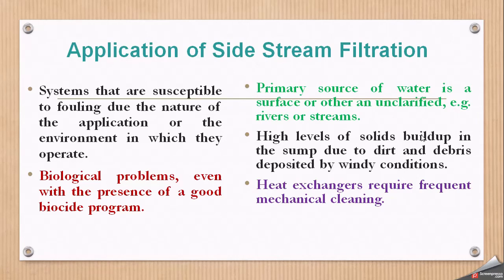High levels of solid buildup in the sump due to dirt and debris from windy conditions or dust storms also require side stream filtration. Additionally, wherever heat exchangers require frequent mechanical cleaning, it indicates significant dirt and suspended particles settling in the heat exchanger tubes and areas, making side stream filtration necessary to reduce that contamination.